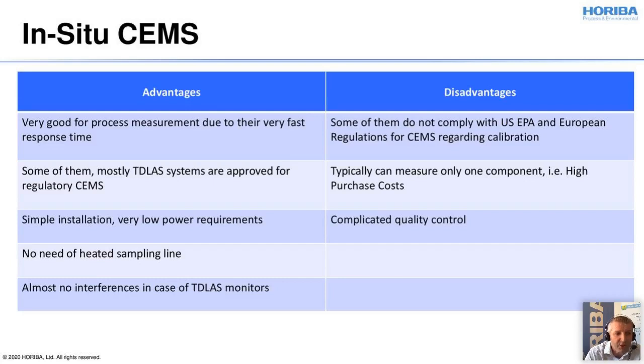In-situ CEMS, of course, have advantages. Some of them, mostly TDLAS systems, are approved for regulatory CEMS as well. We don't need to have a heated sampling line. And for these special components I mentioned before, there is almost no interference in the case of the TDLAS instruments. Unfortunately, not all of them comply with the US EPA and European regulations. Mainly, the reason is the complicated quality control, as you frequently have to check the instrument. And if you have a pass-through, you cannot check the instrument without having the system fully available for calibration.